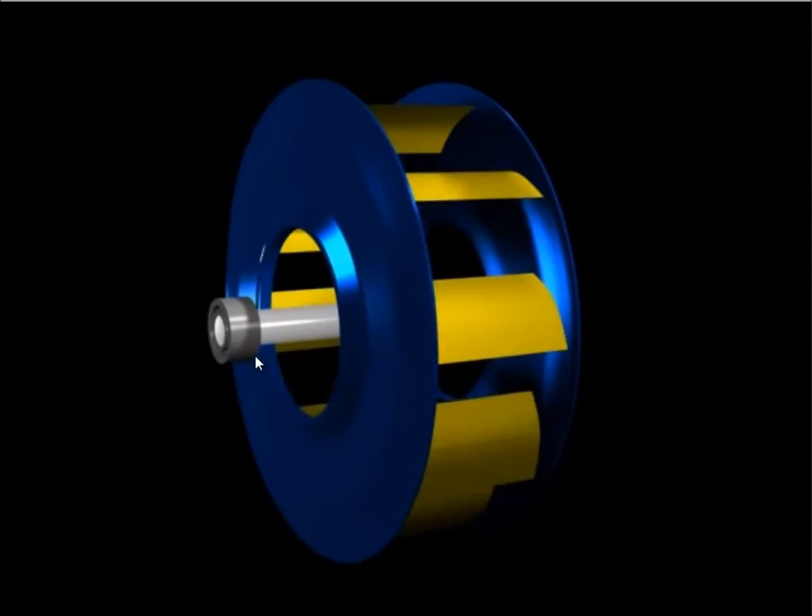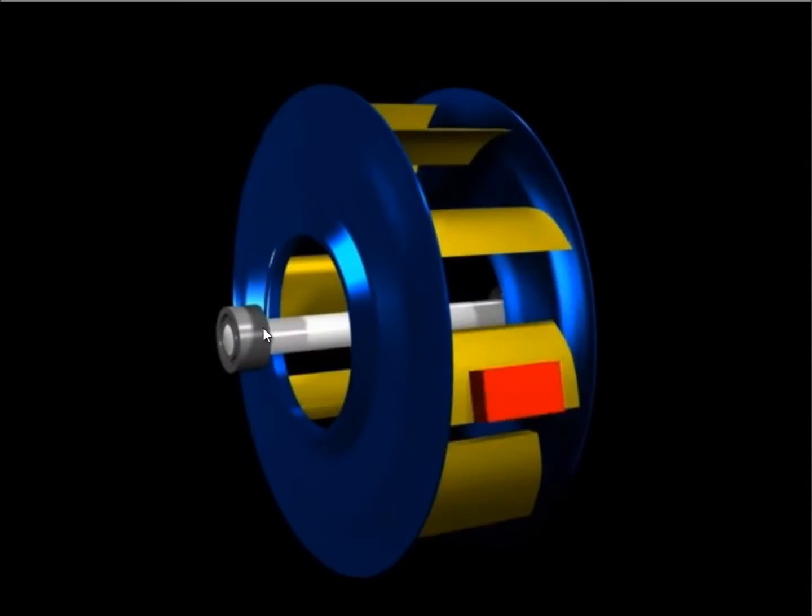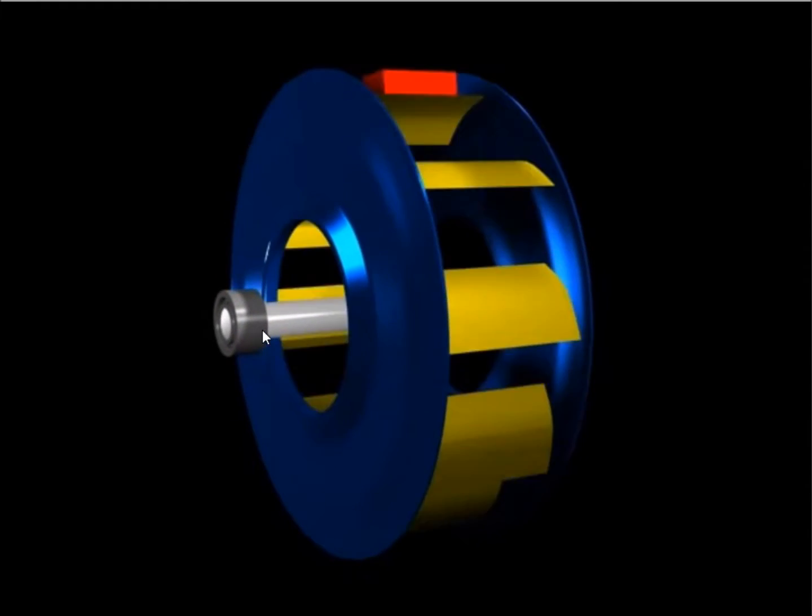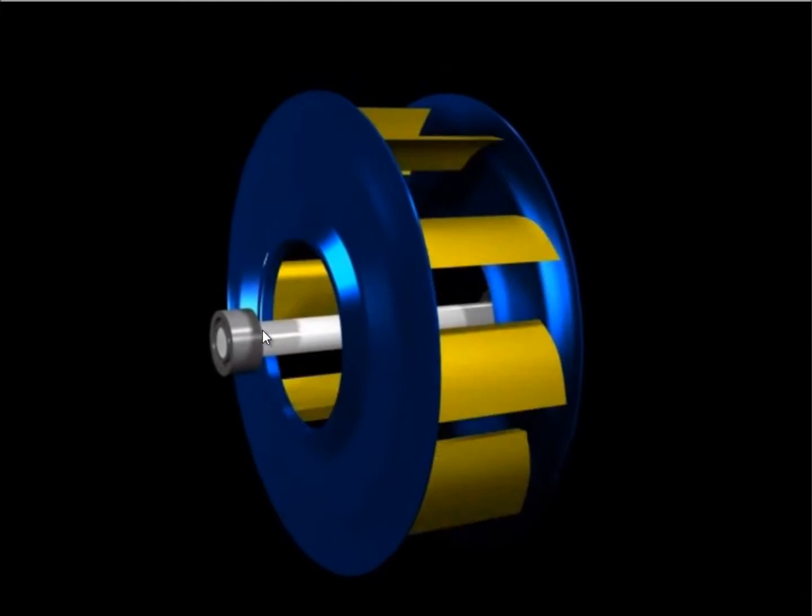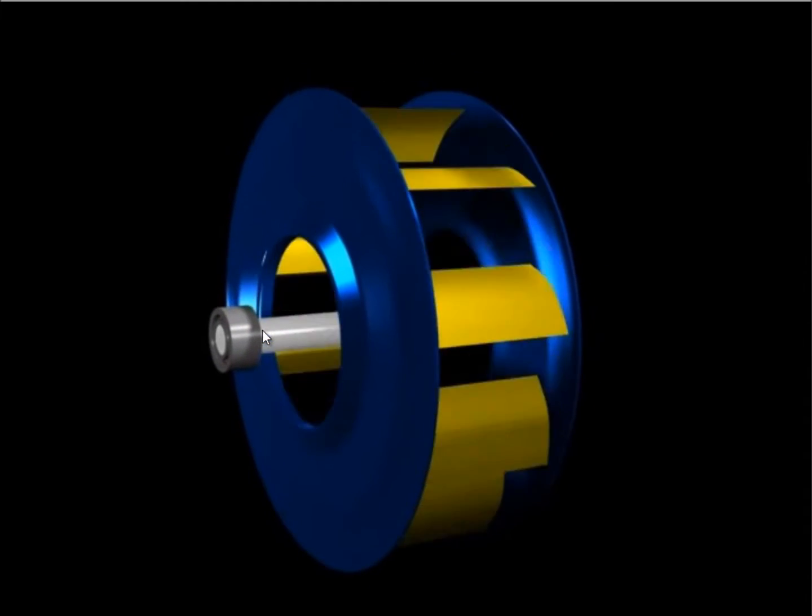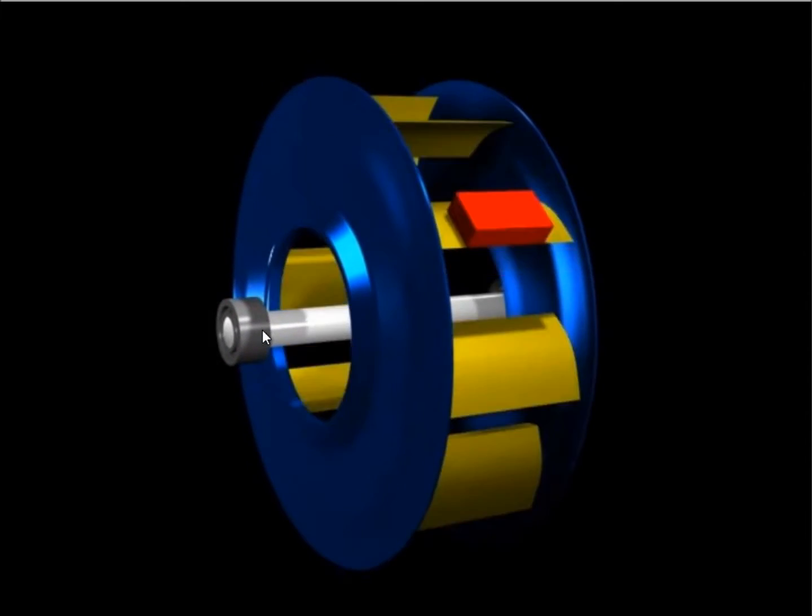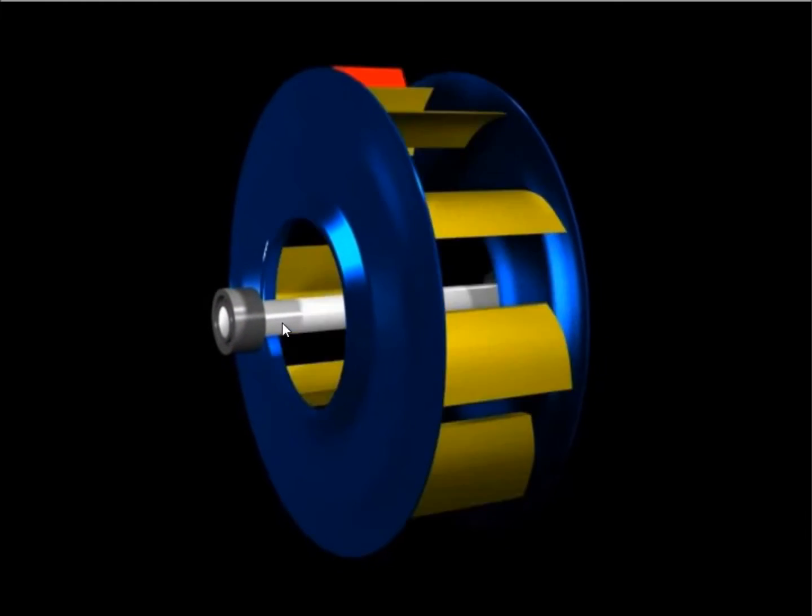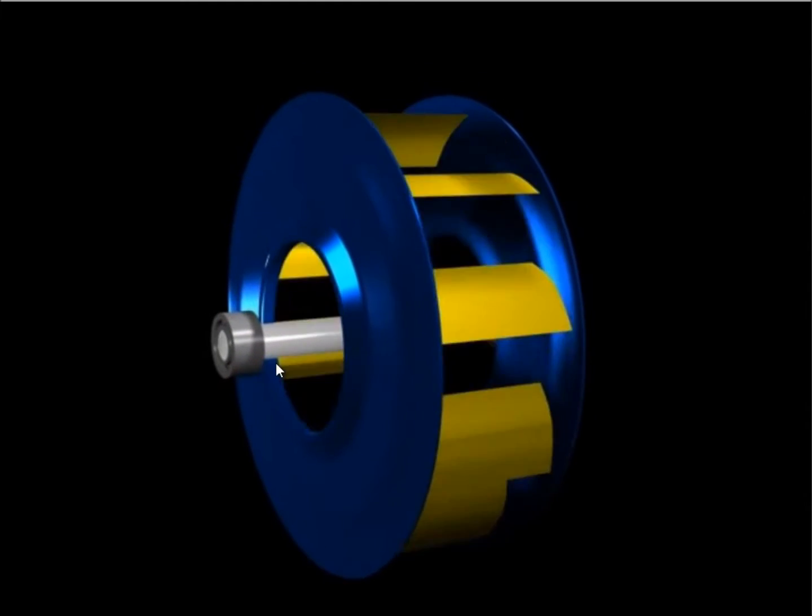Number two, if you look closely, the motion here is circular. And although it may be a little bit elliptical because the stiffness of the machine might mean the horizontal vibration is a little higher than the vertical, basically it's circular and therefore we expect to see 90 degrees between the vertical and horizontal reading.